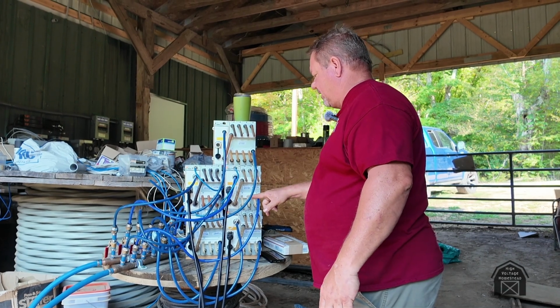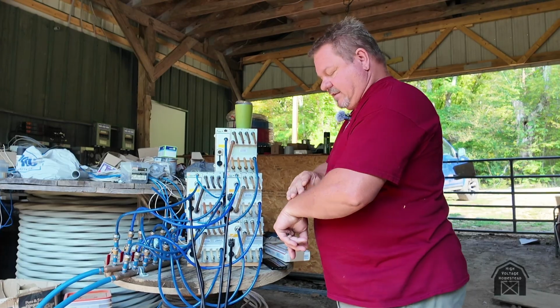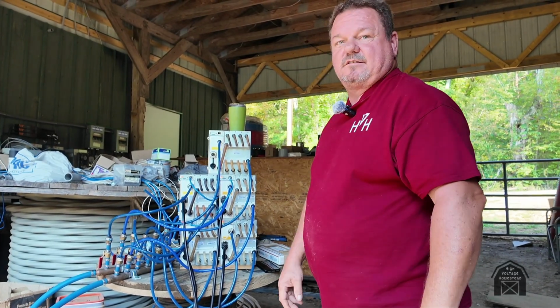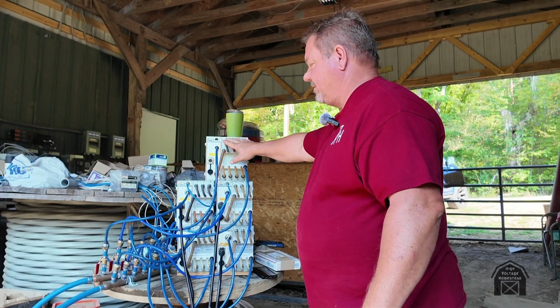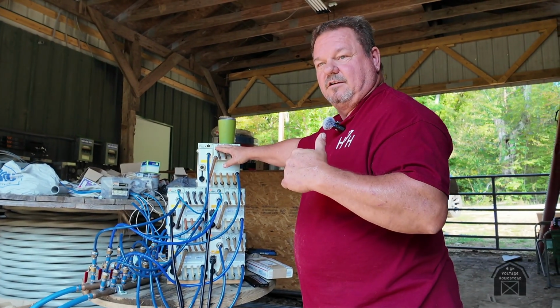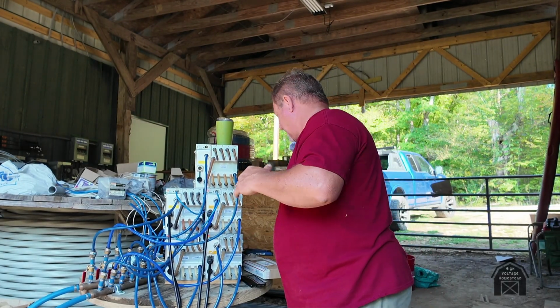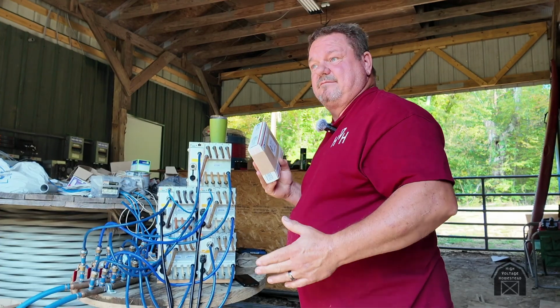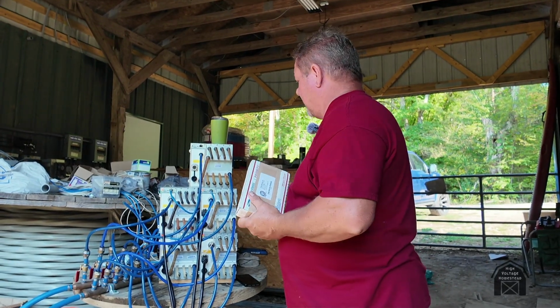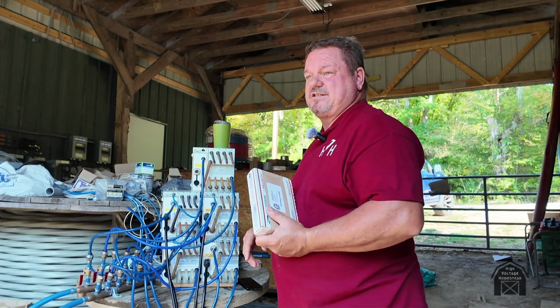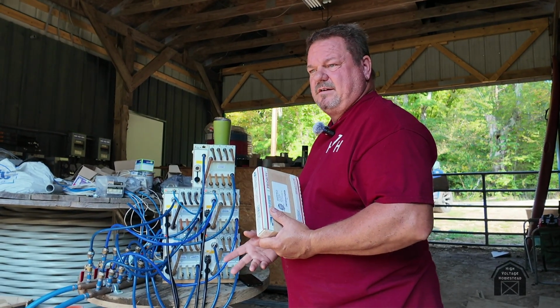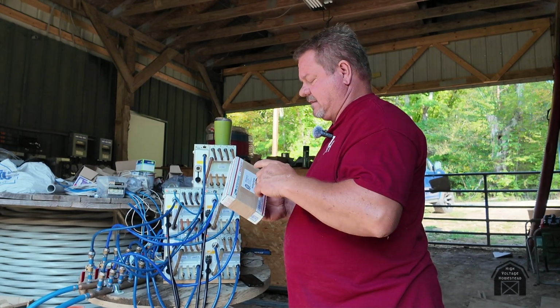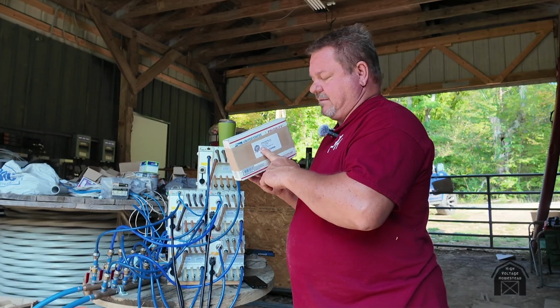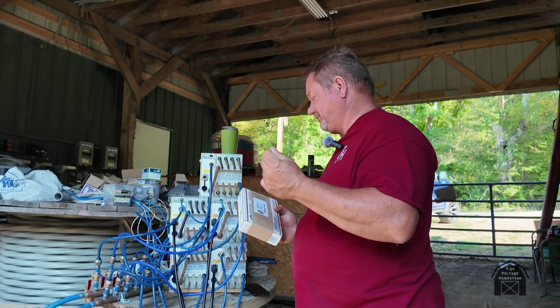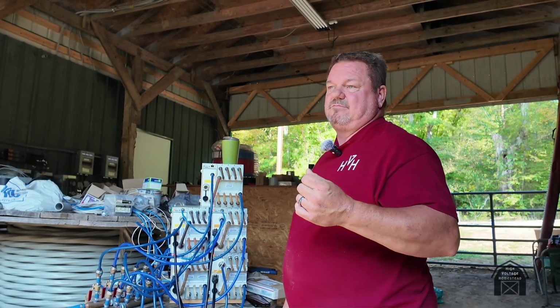Notice all my little lines - when you run even spring water through there, they get all discolored. I do have new lines for everything when I put them on the glycol loop, so we'll get rid of that. My plan, and y'all can throw in some ideas if you want, because these are what you see, but I'm sure inside the heat exchanger there's probably buildup as well. So my plan was, I got some superfine blasting media - it's a little more coarse than flour, not as coarse as sugar.